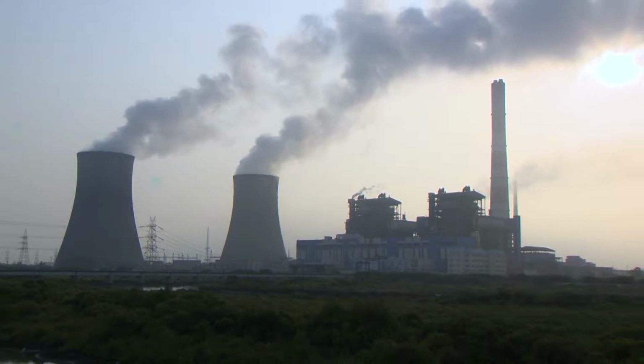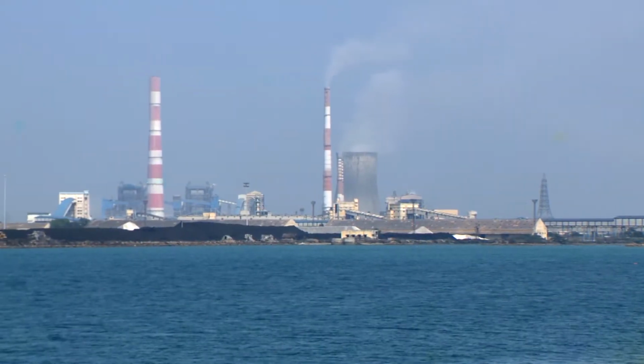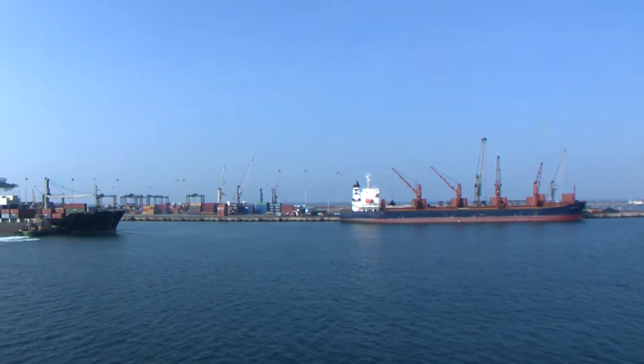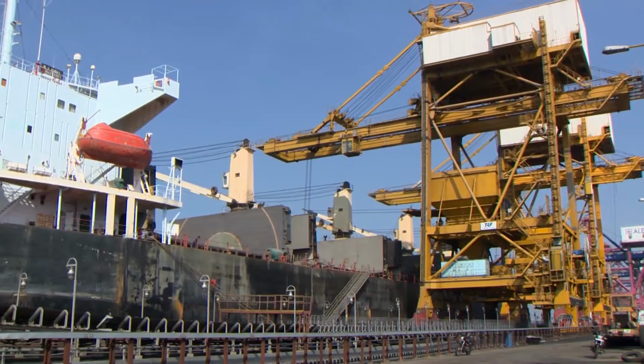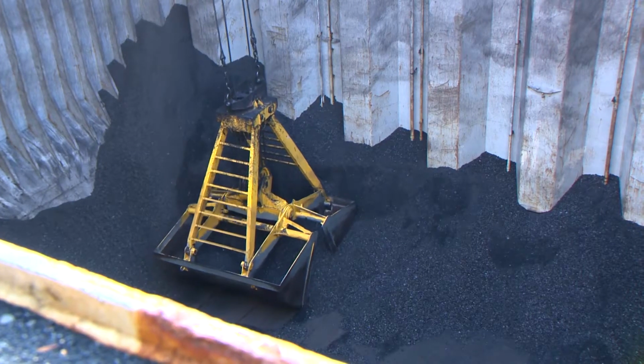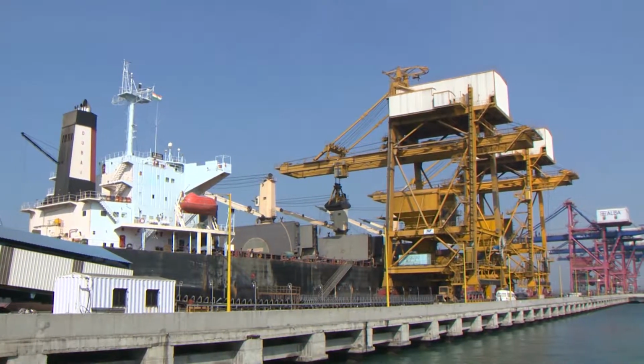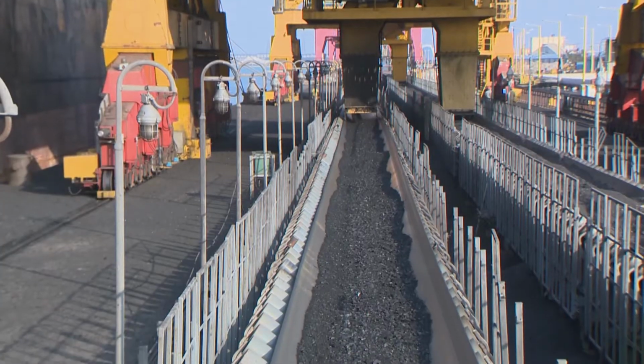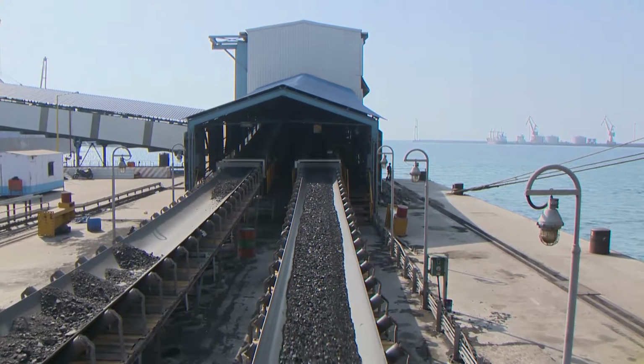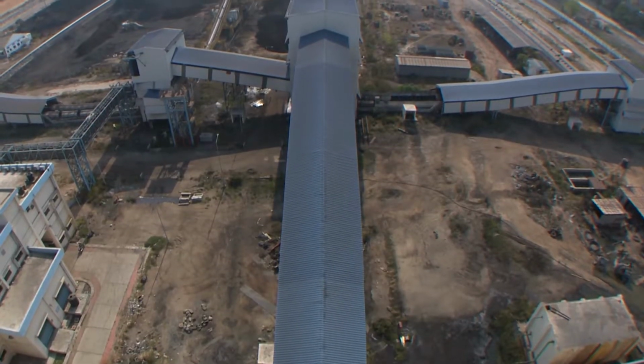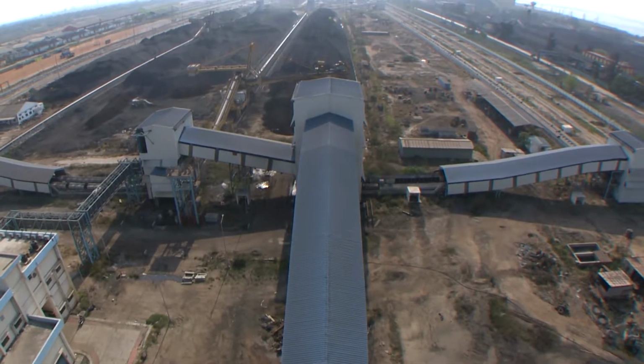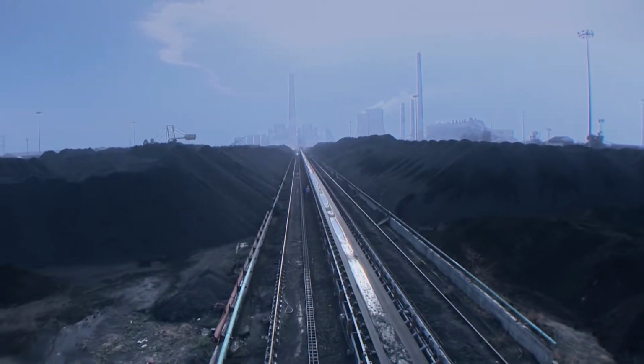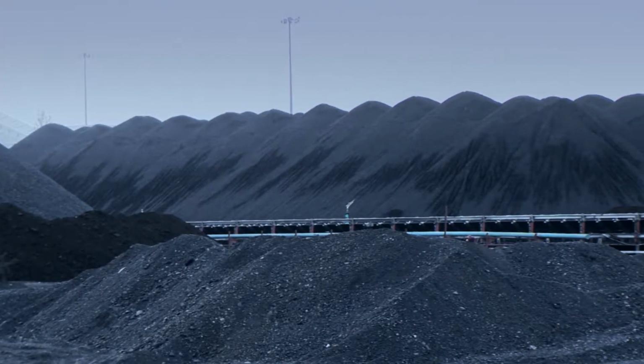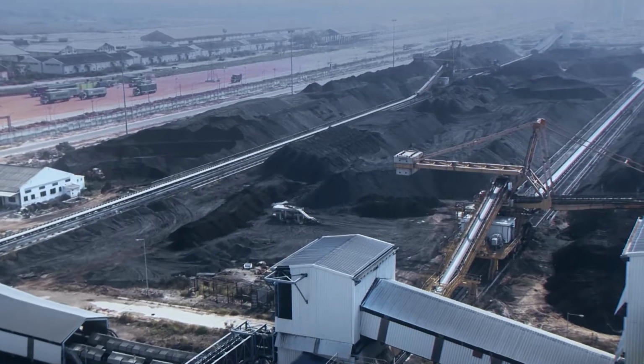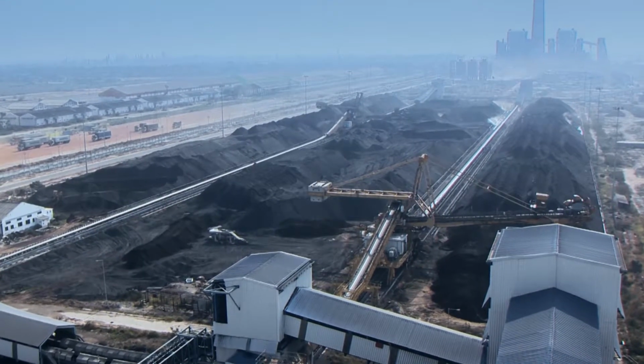Coal handling system. The primary fuel of NLC Tamil Nadu Power Limited is coal. A new coal jetty has been constructed by Tuticorin Port Trust, which will receive coal from ships. Mechanized shore unloaders have been provided to unload coal from ships and to load it to jetty conveyors. Coal will be conveyed up to the crusher house through a double stream of conveyors. Provision has been kept to send coal either directly to boiler bunkers or to the stockyard. The coal stockyard has a storage capacity to meet the 30-day requirement of both the units. In the coal storage yard, 2 stacker cum reclaimers have been provided along with the conveyors.